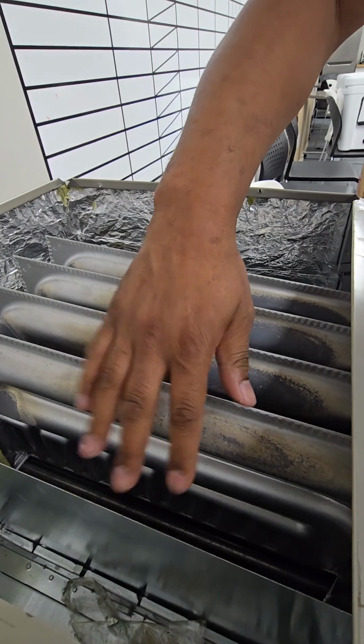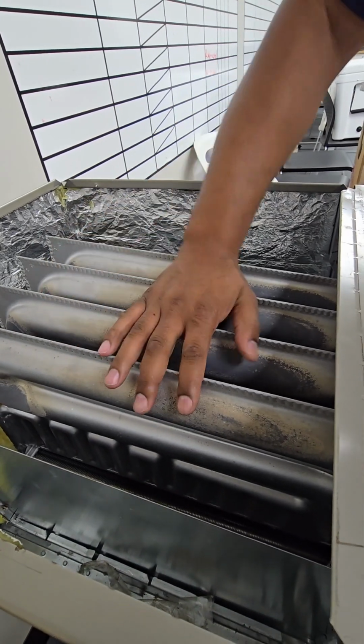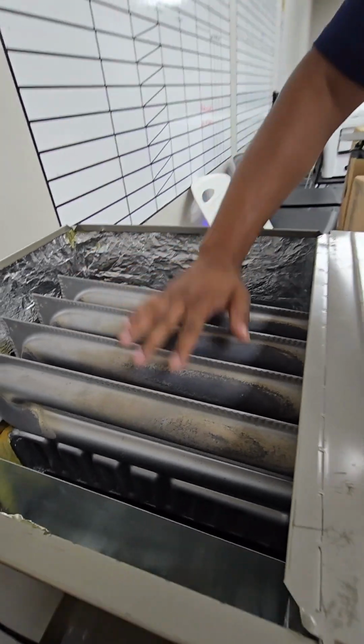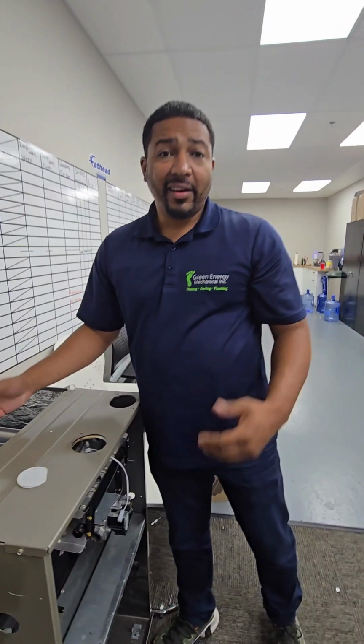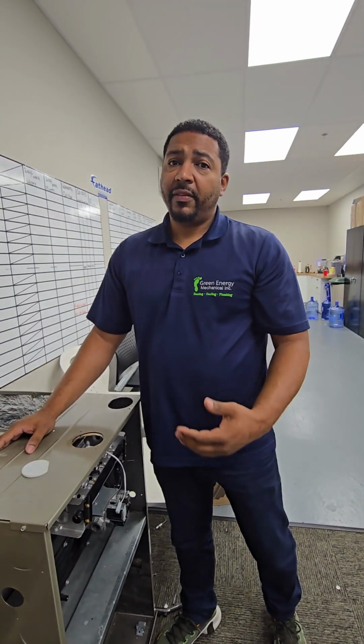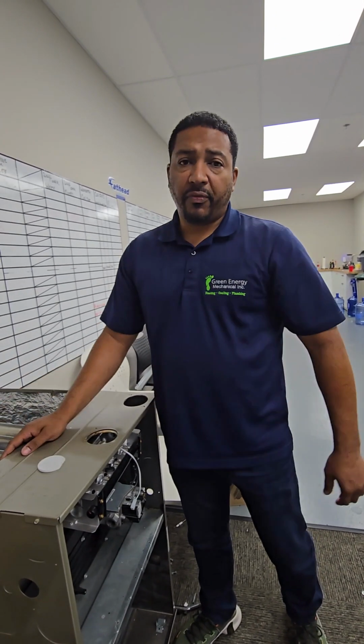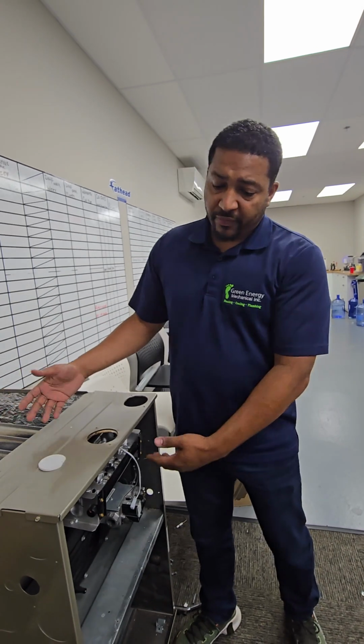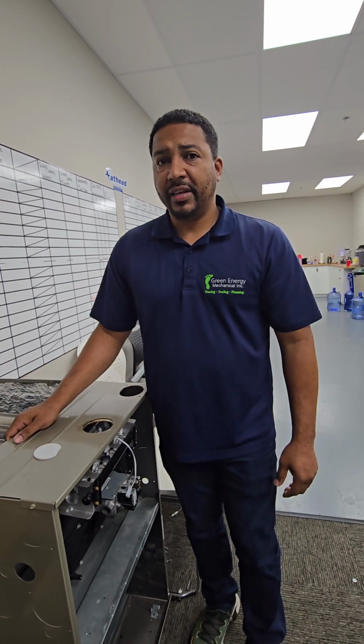Now, if this doesn't get enough air over it, these will actually overheat. And if they overheat too much, they're going to crack. And if it cracks, then you could have carbon monoxide poisoning. Hopefully not too bad, hopefully it gets caught before then. In this case, we were able to catch it before it actually did crack, but you could see from inside it had major issues.